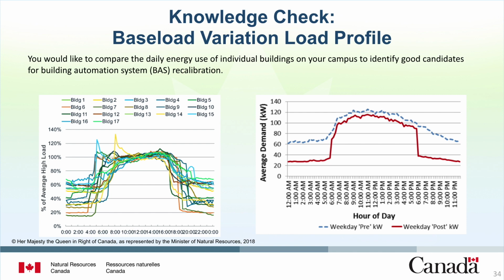You would like to compare the daily energy use of individual buildings on your campus to identify good candidates for building automation system recalibration. Which load profile type is best for the analysis? Select option 1 or 2. The correct answer is option 1. Use a base load variation load profile to compare the average weekly electricity use of multiple individual buildings. Option 2 is incorrect. It is a weekday load profile with base load improvements, which can be used to confirm that recent improvements have made anticipated changes to a single building's baseload energy use.